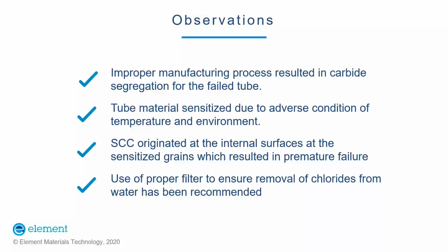A valuable takeaway for our client from this study was to take a more cautious approach to the manufacturing process of the heat exchanger, especially the tube. They will advise their supplier to monitor the fabrication steps of the tube. Better control will be implemented to monitor the operating condition of the heat exchanger, and we also advised the client to use proper filtration to ensure removal of chlorine from the water.